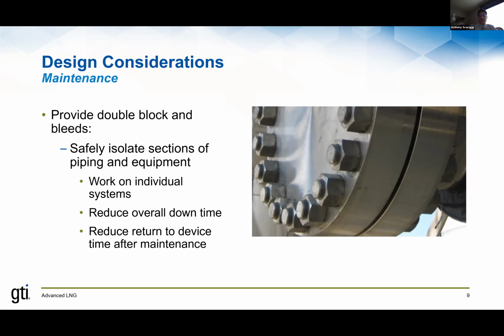To be able to do maintenance on these systems, and to be able to do it safely, there's a very, very common method called providing a double block and bleed. So equipment that would be worked on needs to be isolated from the LNG source. So you could close a valve and isolate LNG moving into that piece of equipment, but you don't want to just rely on that valve for safety purposes. Any kind of leakage by that valve could be a hazard to somebody working on equipment downstream of that valve. So you then have a way to vent that pipe downstream of that valve, and then you close another valve on the other side of that vent. So you have two valves stopping the flow of LNG, and in between those valves you have a vent, so that if any LNG passes the first valve, it doesn't pressurize the second valve. It actually is removed from the system.